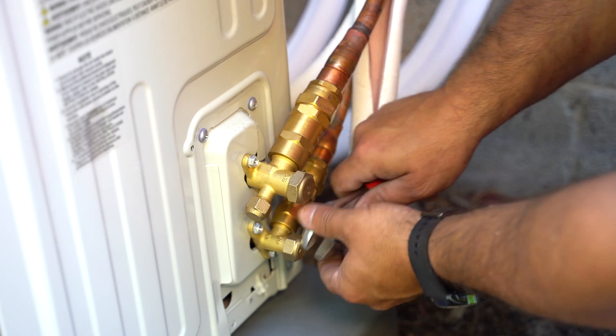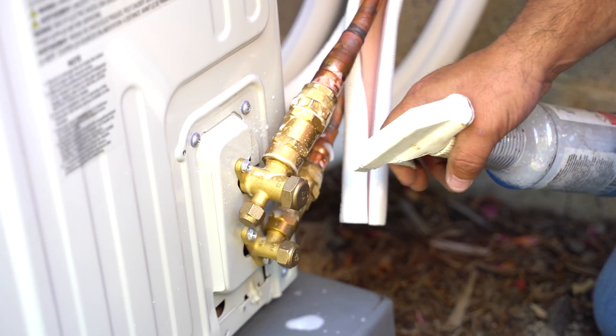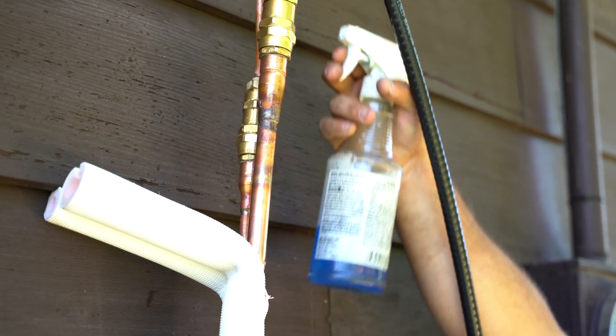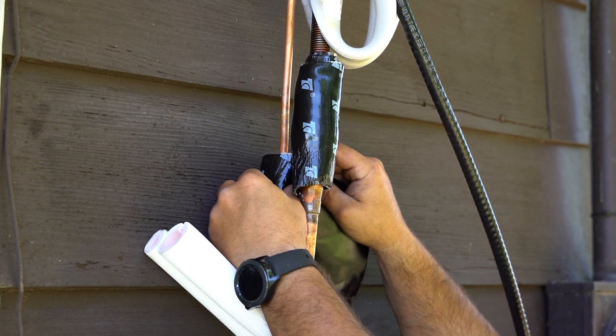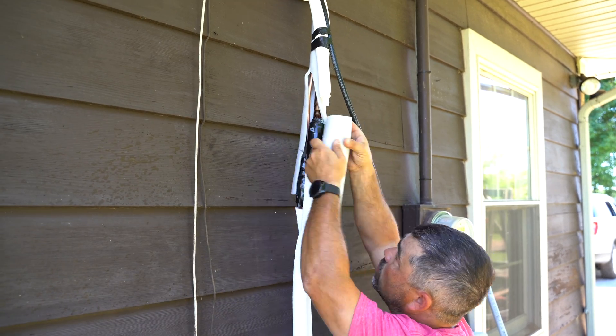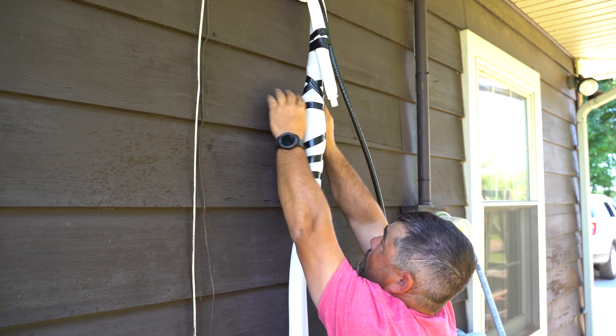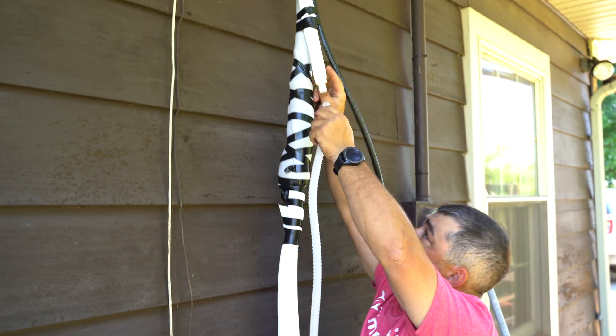Replace the valve covers. Use soapy water at both the condenser and air handler refrigerant connections to check for leaks. Wrap the refrigerant connections near the air handler with foam pipe insulation. Then connect the condensate drain hose securely.